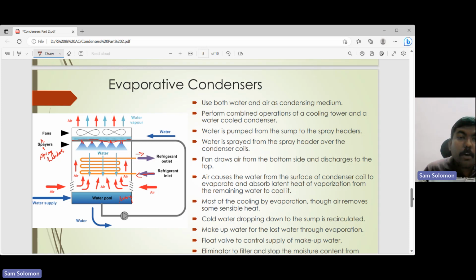And we also have a fan at the top. So you can see this is the fan over here. Two fans are mentioned here, so it can be either a single large fan or multiple fans. This fan sucks in air through these openings, and the air is taken in. And this air, as it blows past the condenser coil, carries away the water droplets that have settled over here.